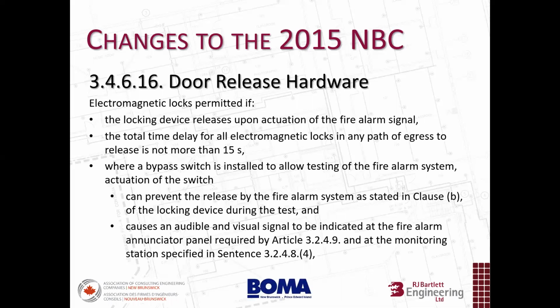So just go through these. Electromagnetic locks are permitted if the locking device releases upon actuation of the fire alarm signal. The total time delay for electromagnetic locks in any path of egress to release is not more than 15 seconds. This is also new. The previous version of the code limited the application of electromagnetic locks to exit doors only. Now we have a clarification that you are permitted to have them within your egress routes as well. So you can have these delayed egress doors, but if you have more than one of these between a certain portion of your building and an exit, the cumulative delay of these doors cannot exceed 15 seconds. So you're only allowed to delay up to 15 seconds.